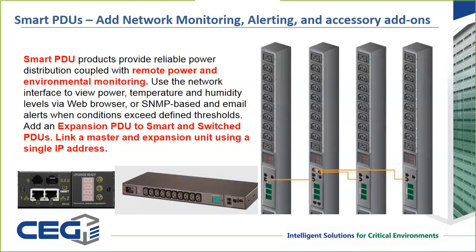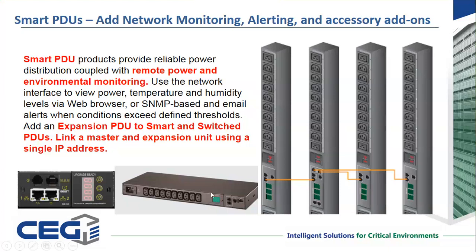So you can see, in addition to the meter that's on these power strips down here, here's an exploded view of another manufacturer's, and you can see the network connections on the power strips. Some of them, like this Geist meter, have 2 network connections, a backup network connection for added redundancy. The things that look like RJ11 jacks, the phone jacks that we have in our homes, that's where an accessory like a temperature humidity sensor would plug into a power strip. A lot of manufacturers' smart power strips have the ability for you to plug in an accessory, and the most common accessories are temperature and humidity.